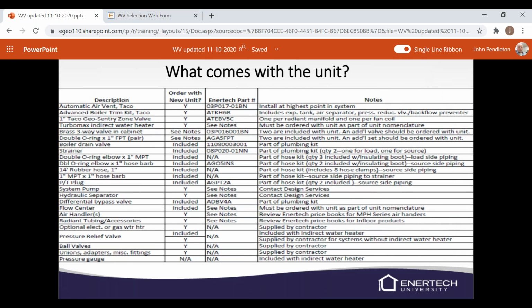So in the unit, these are all the parts and pieces that are going to come with it when you order it, depending on the type of unit that you have. So there'll be zone valves, turbomax tanks, double O-ring fittings, strainers, that kind of thing. So this is also listed in the manual, and there are some notes that, like if you got an automatic air vent, it needs to be installed in the highest point of the system. Here's our part number, should you order it with a new unit, and so forth.